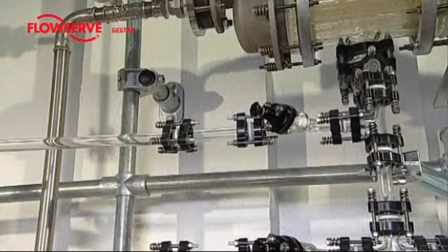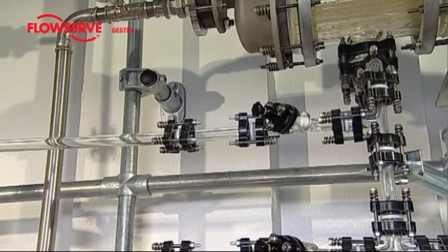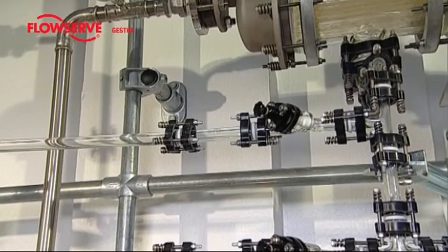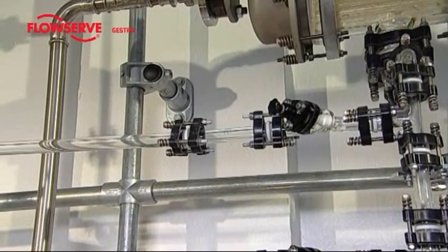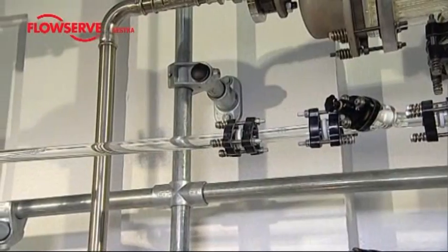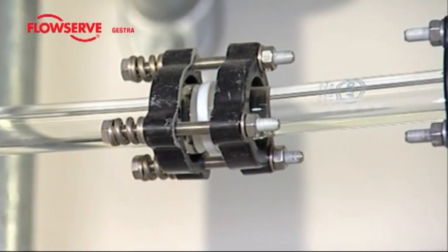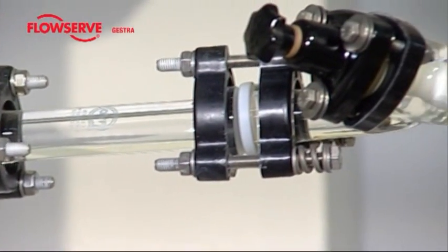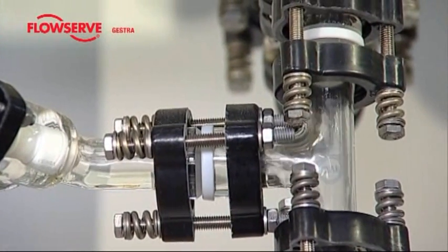In this film clip, the origin and effect of thermal pressure pulses, generally known as Waterhammer, will be demonstrated. For this, steam is introduced into a horizontal glass tube with a slight upward inclination, thus forming a pocket of water. The water enclosed in the tube on the left-hand side is cold, whereas steam is available on the right-hand side. This represents a typical startup situation for pipe segments with poor drainage.